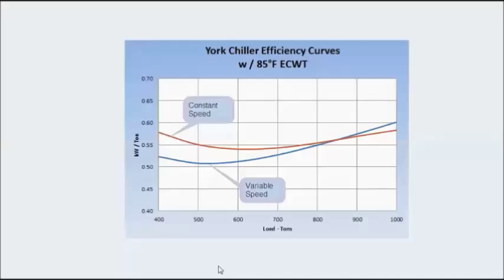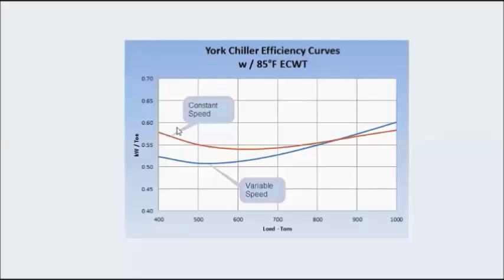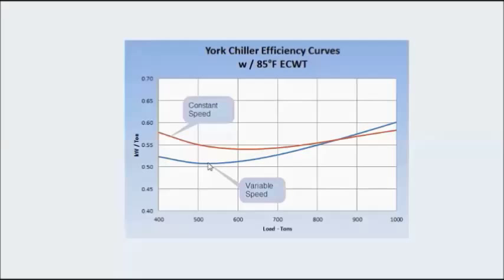Let me now show you a couple of the chiller curves. Here we have two curves for the same chiller except that the first one is operating with a constant speed drive motor and the second one, the lower one, is a variable speed. These two curves came from York calc for the same chiller. You can see the improvement at part load with efficiency.